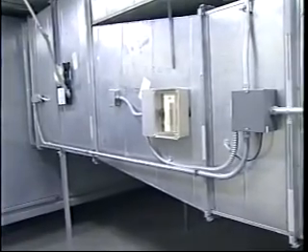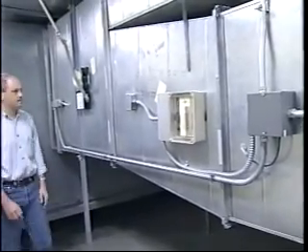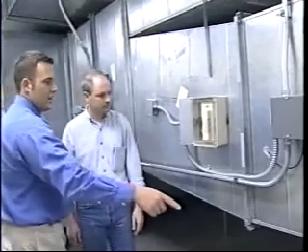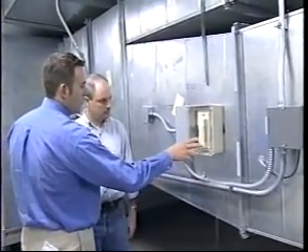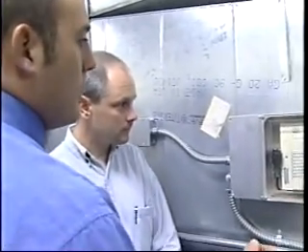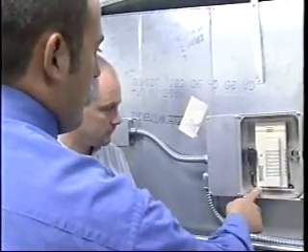So how was the team able to solve the problems found as a result of the walkthrough? We made a recommendation for them to recalibrate the carbon dioxide sensors on the return air. The vocal music room did have high levels of CO2 when we did our walkthrough. So essentially we told them to lower the set point on the carbon dioxide sensor.